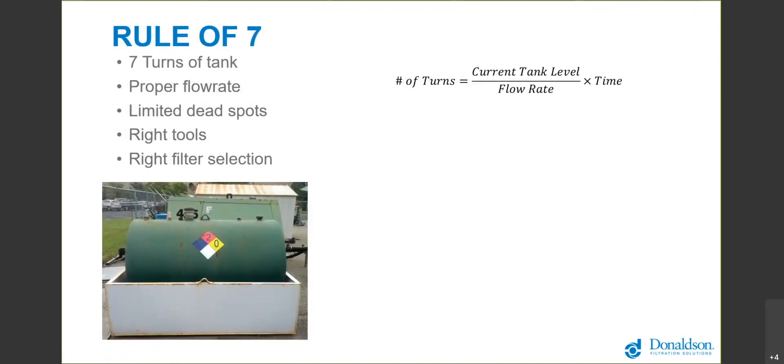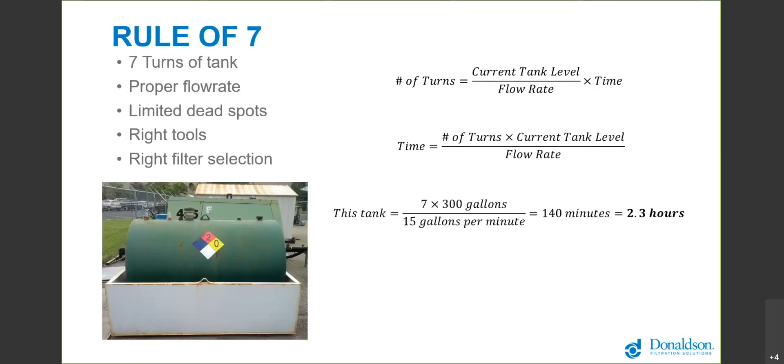Typically in the hydraulic world they use the rule of seven, which means you have to take a volume of fluid and flip it seven times in order to clean it up with the right pump, the right filter, the right tools.